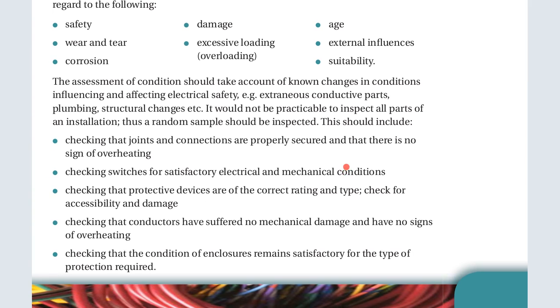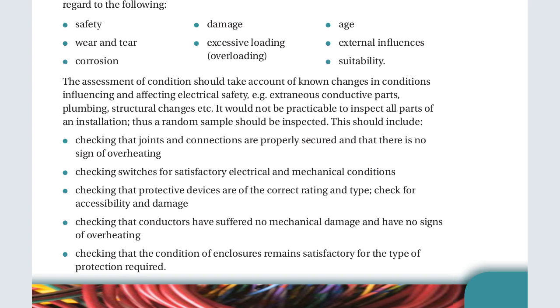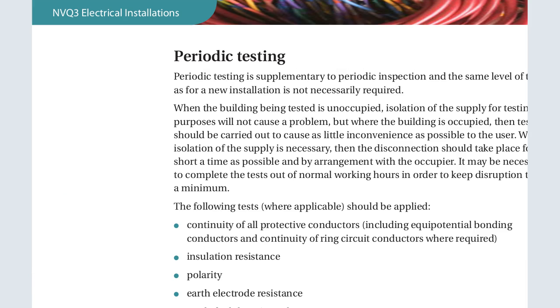So this should include checking that the joints and the connections are properly secured and that there is no sign of overheating, checking switches for satisfactory electrical and mechanical condition, checking that protective devices are of the correct rating and type, checking accessibility and damage, checking that conductors have suffered no mechanical damage and have no signs of overheating, and checking that the condition of the enclosure remains satisfactory for the type of the protective requirement.